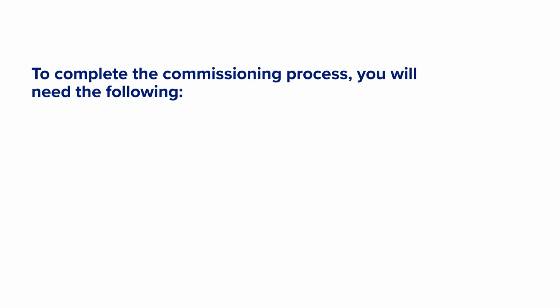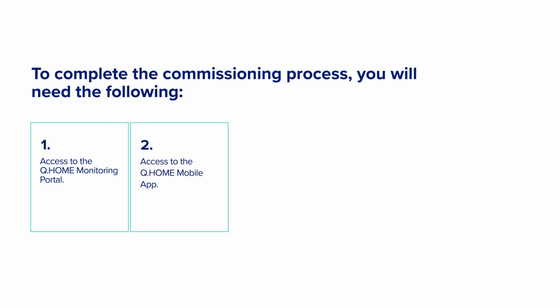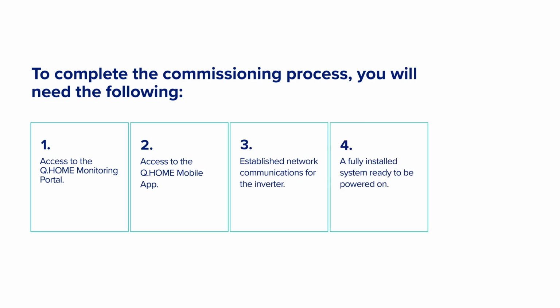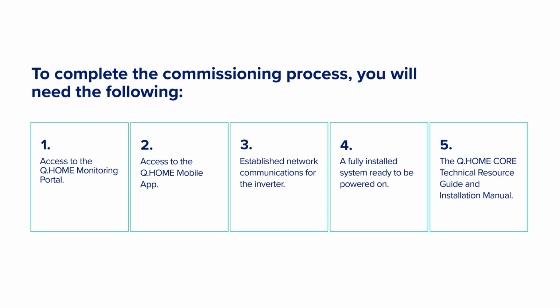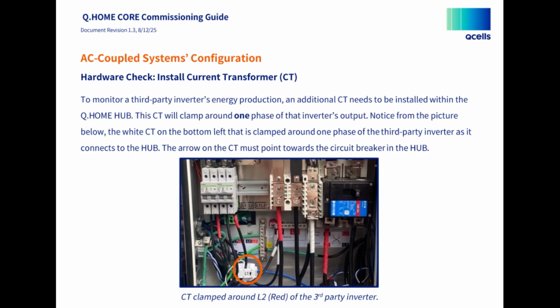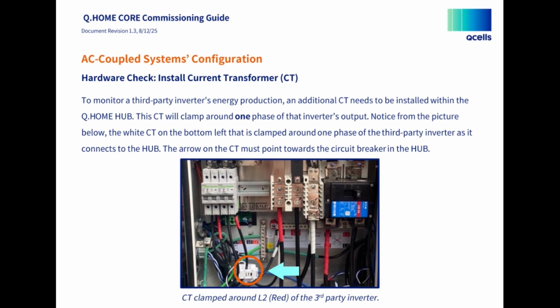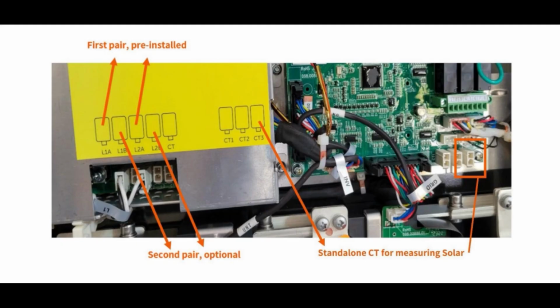To complete the commissioning process, you will need the following: access to the Q.HOME monitoring portal, access to the Q.HOME mobile app, established network communications for the inverter, a fully installed system ready to be powered on, and the Q.HOME CORE Technical Resource Guide and Installation Manual. It's important to note that the AC-coupled configuration requires an external production CT to be installed and landed in the hub to capture the AC-coupled system's energy generation. The external production CT is not included with the hub and must be purchased separately.